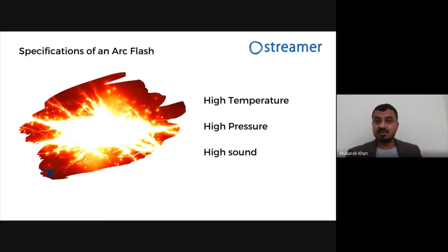So arc flash has a very high temperature, a very high pressure and a very high sound. The temperature is around 20,000 to 36,000 degrees Celsius. Some specifications say 20,000, some say 36,000. But one common thing known is that this is around 4 times the temperature of the surface of the sun. This temperature can vaporize almost everything. Any known material will vaporize at this temperature. This is a very, very high temperature.